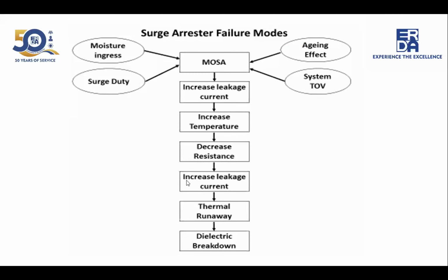As I told you, for metal oxide surge arresters, moisture ingress is there, then surge duty is there, so a number of lightning surges impact the surge arresters. Then the aging effect is also there, as well as some temporary overvoltages in the system. All these parameters affect the surge arrestor condition. So it will increase the leakage current of the surge arrestor due to all these environmental effects and aging effect. As a result, when the current increases, the temperature of the surge arrestor also increases.